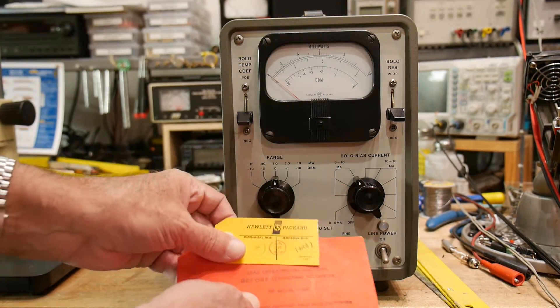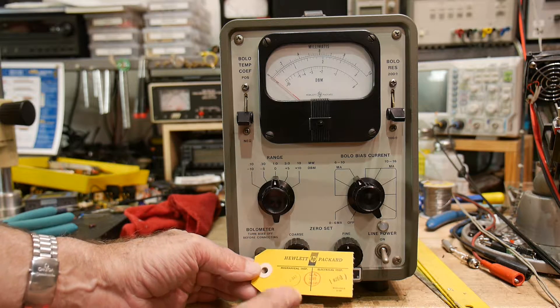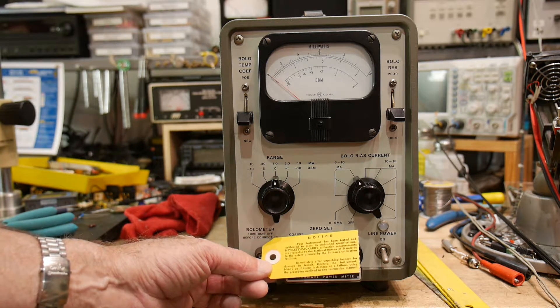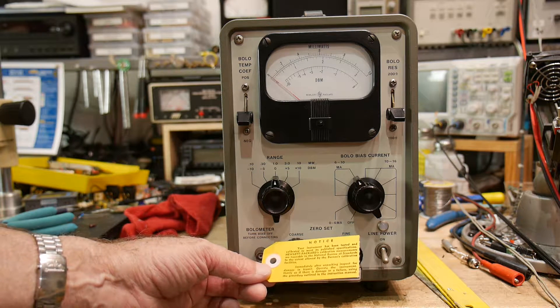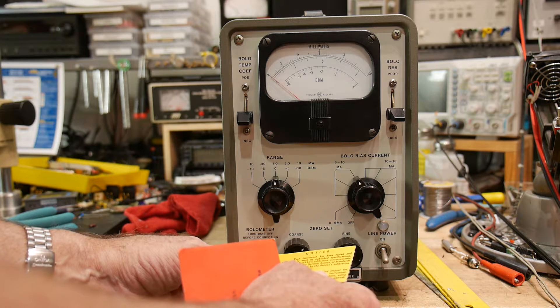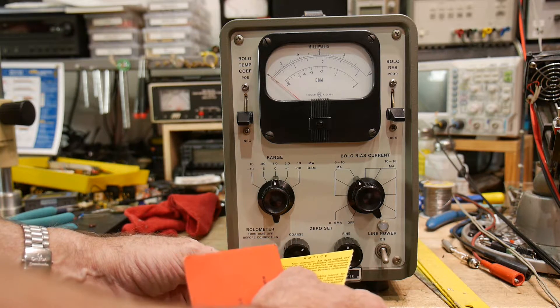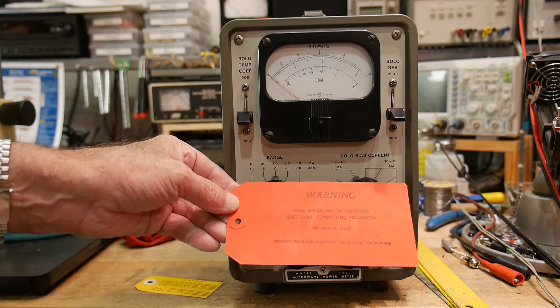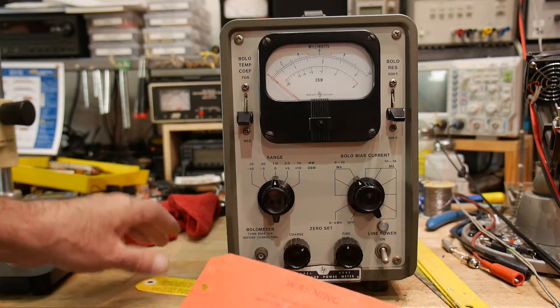It has a couple of cards that came with it saying it was inspected. The card is labeled May of 1968 — that's when it was printed at least. It reads: 'Your instrument has been tested and calibrated to meet its published specifications. Hewlett-Packard's calibration measurements are traceable to the National Bureau of Standards.' It also comes with a big red warning sticker: 'Read operating instructions before connecting bolometer.' I guess you can damage the bolometer if the settings are wrong, maybe the bias is too high.